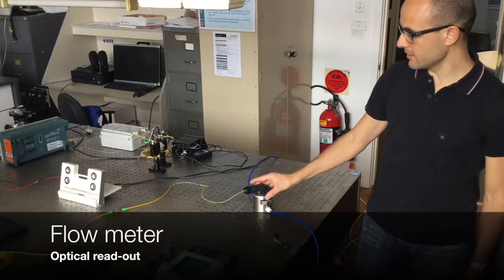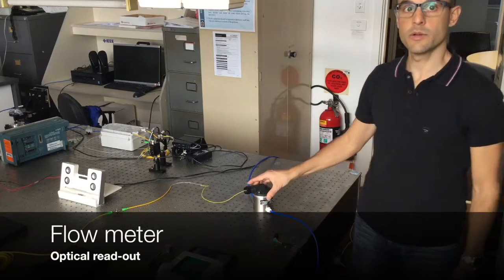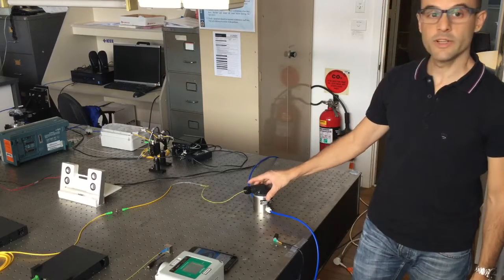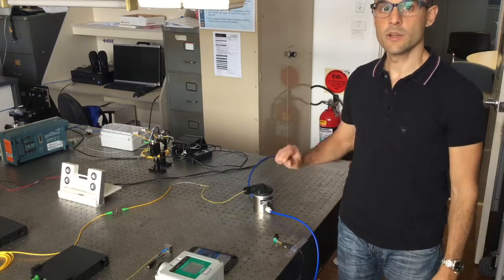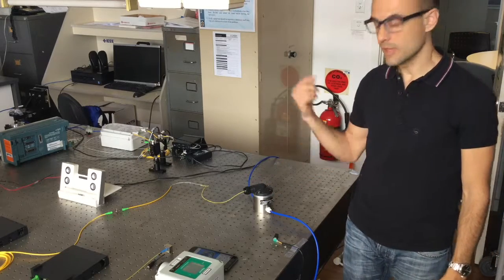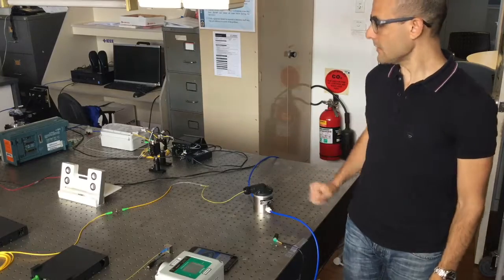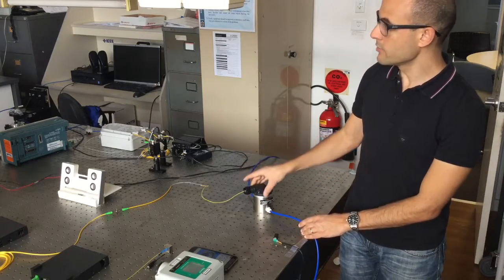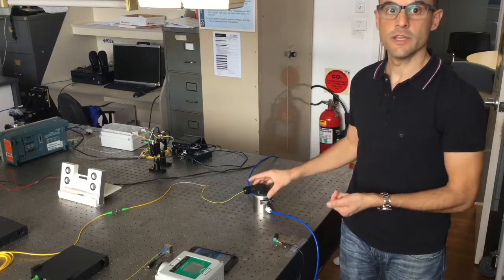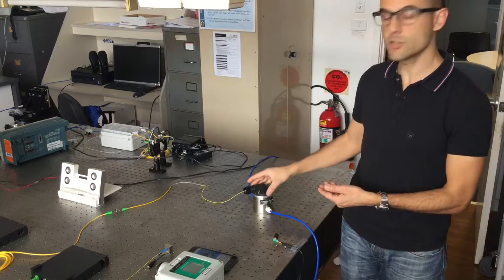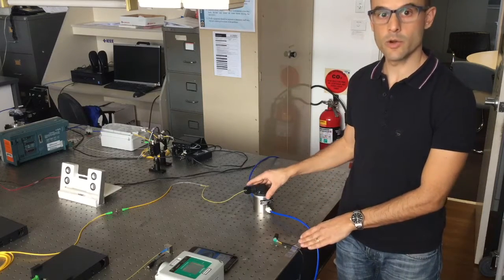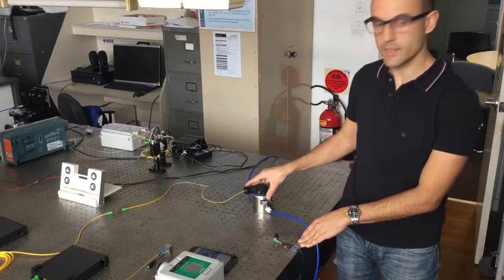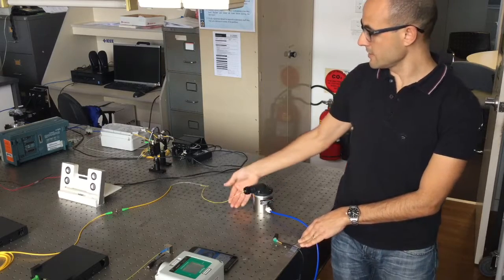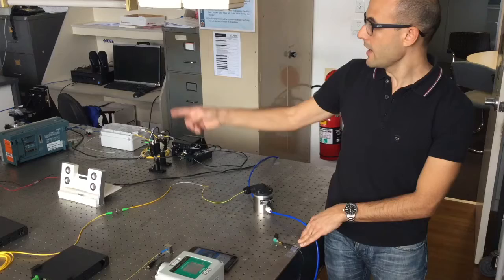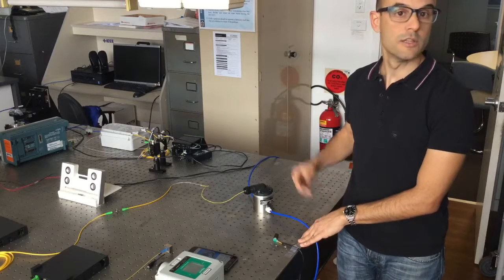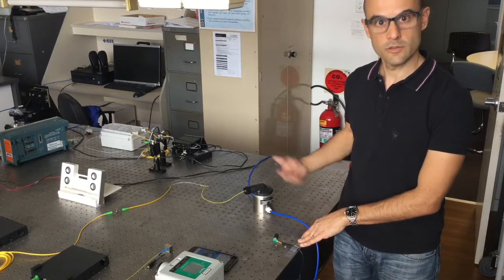This is a flow meter that we also have retrofitted with our optical transducer. It's an oval gear flow meter that opens and closes a circuit every time the wheel turns. In this case, we convert that open-closed circuit into pulses, and then the electrical pulses are applied to one of our optical transducers that sits inside the case. Then the signal is read optically, and the pulses are counted so that we can retrieve the flow rate.